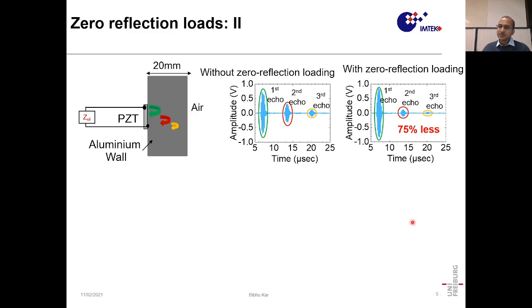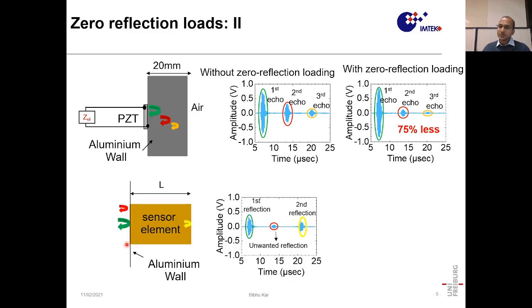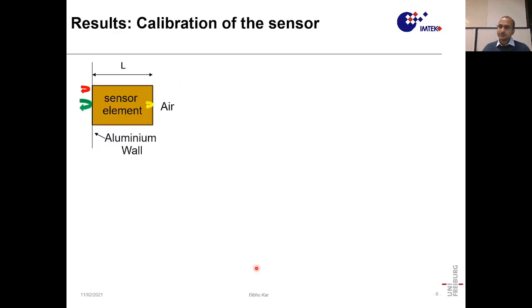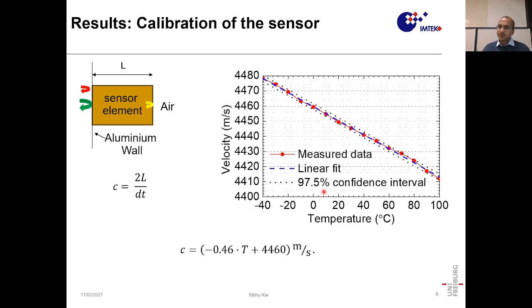Now we attach a sensor element coaxially to the other side of the aluminum wall and do a pulse echo measurement to calculate the time of flight in the sensor element. By measuring the time of flight, acoustic speed in the sensor element can be calculated using this equation. This figure shows the calibration results of the brass sensor element. We saw a linear dependency between acoustic speed and temperature, which follows the following equation.